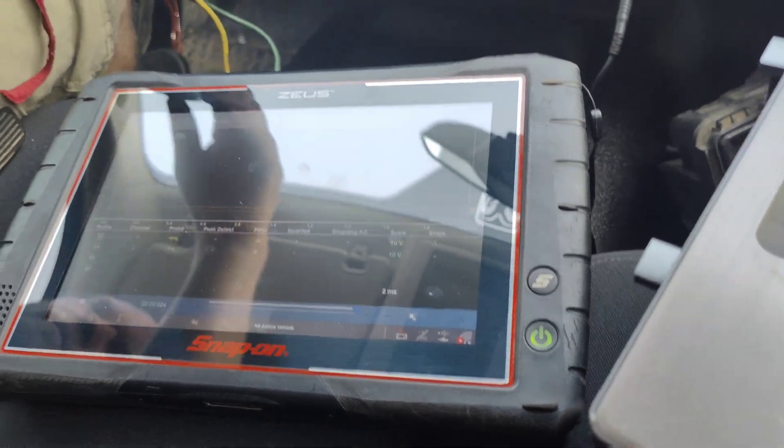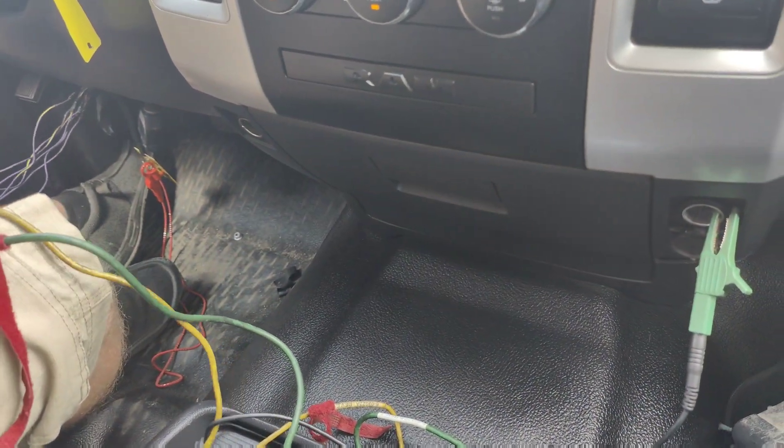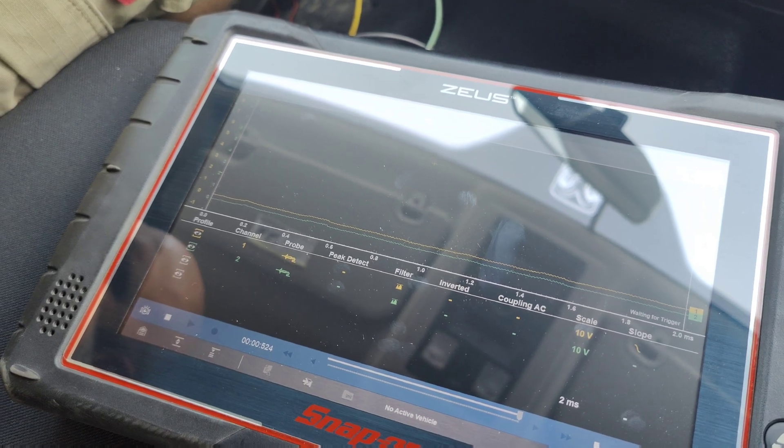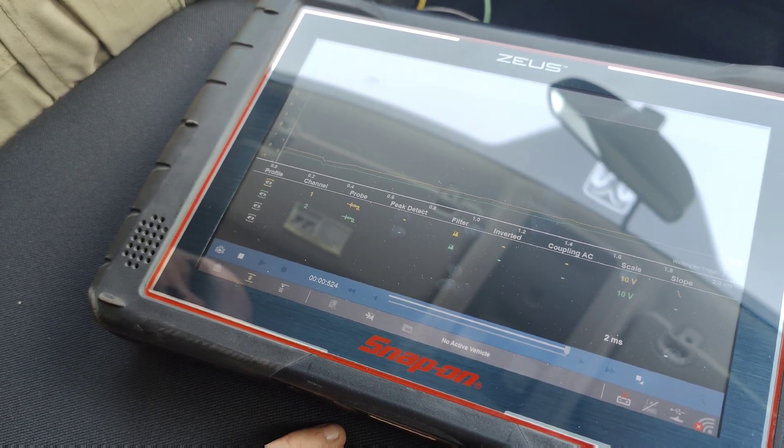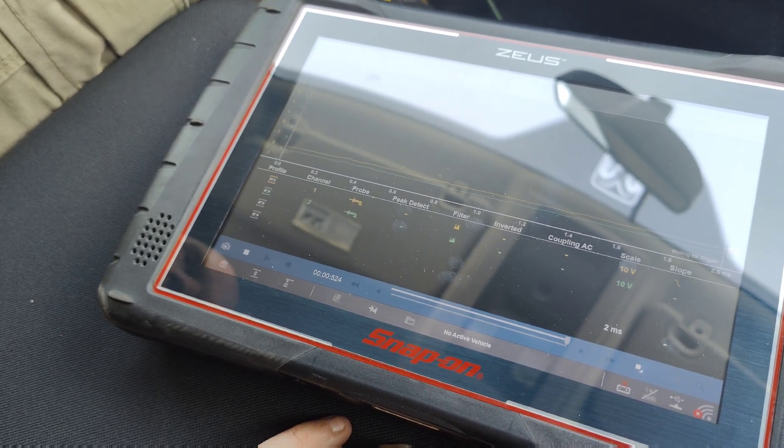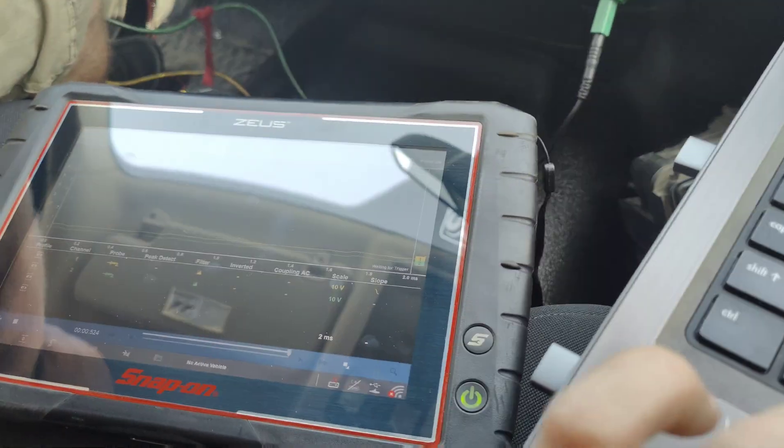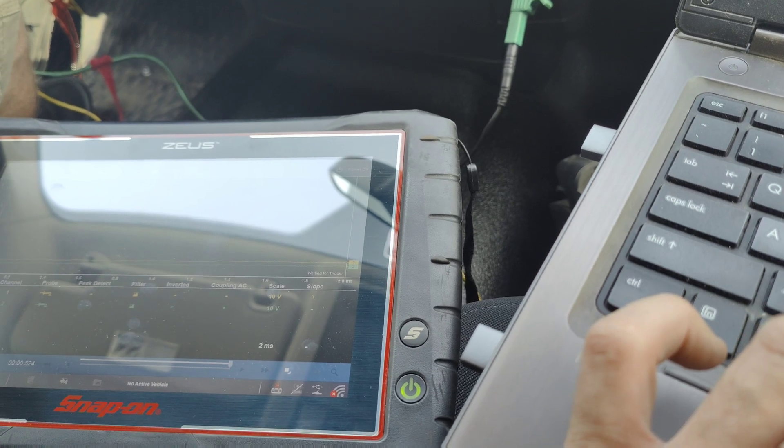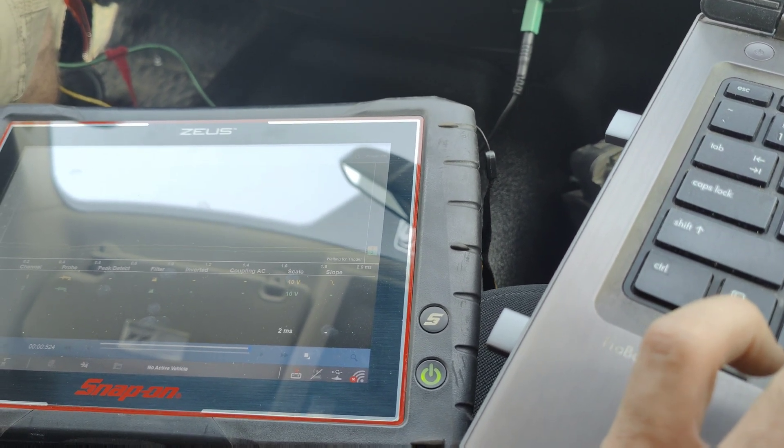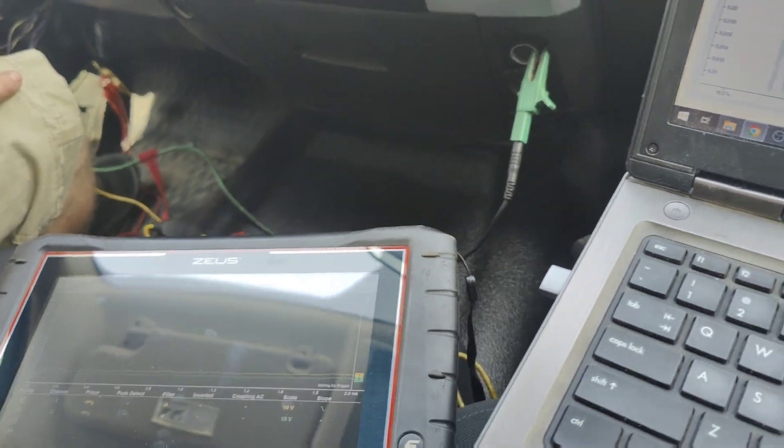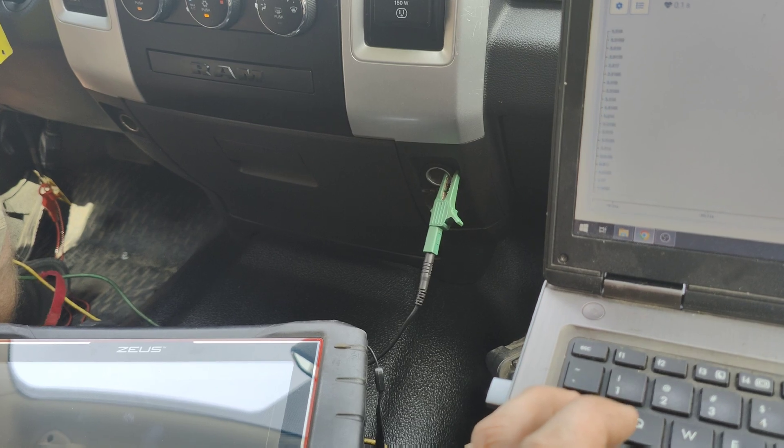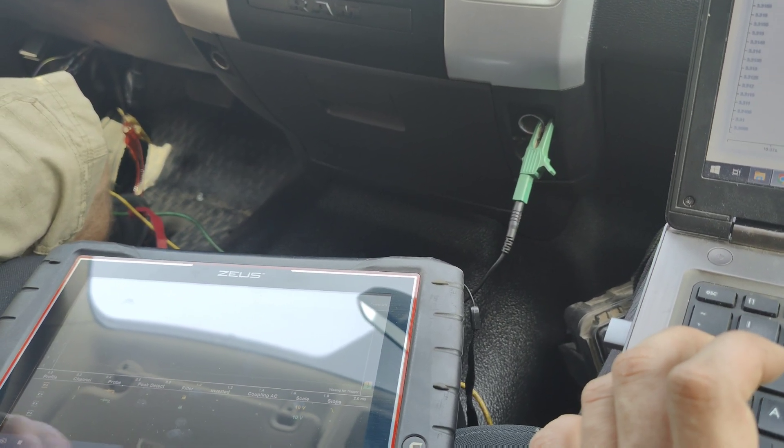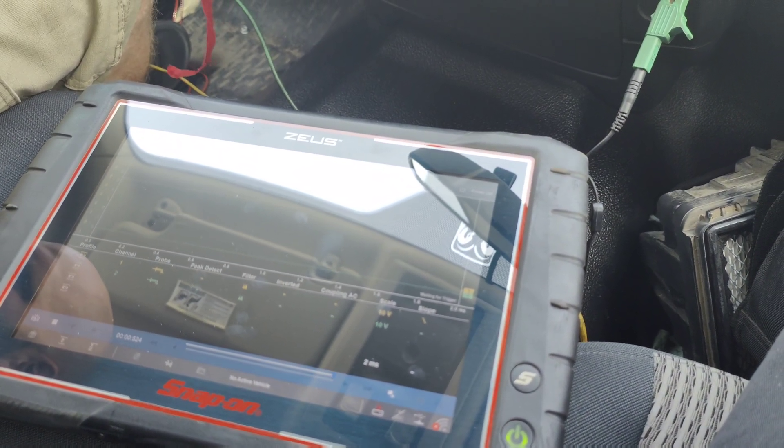Yeah, we have nothing on them now. So when you plug it in we should have something. No, we have nothing. This is our signal? Yeah. We got nothing. Move your pedal. Nothing. Is that what it shows on scan data too? Scan data's showing 3 volts on APP2. Go back to our signals. Where are our signals? I mean, not the signals - the feeds. Make sure we still have 5 volts because we didn't check them with the circuit complete.